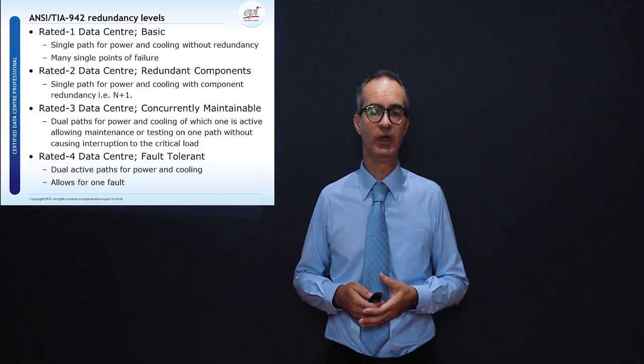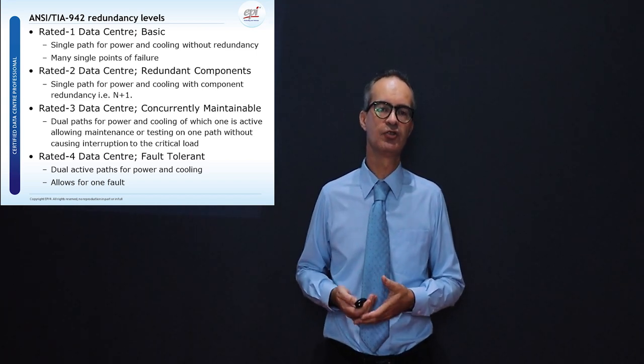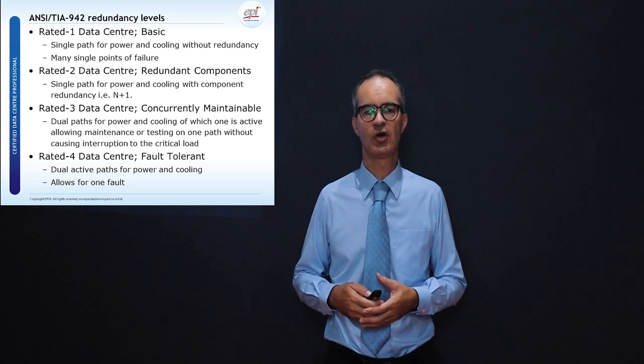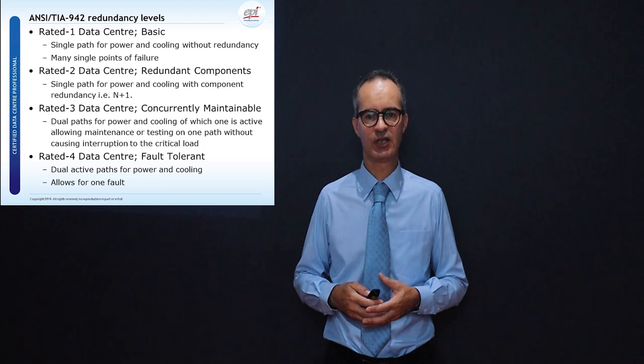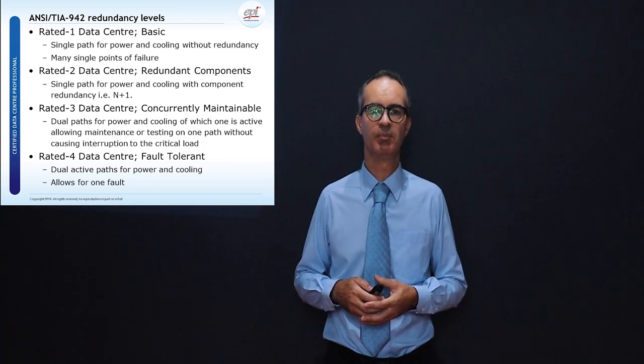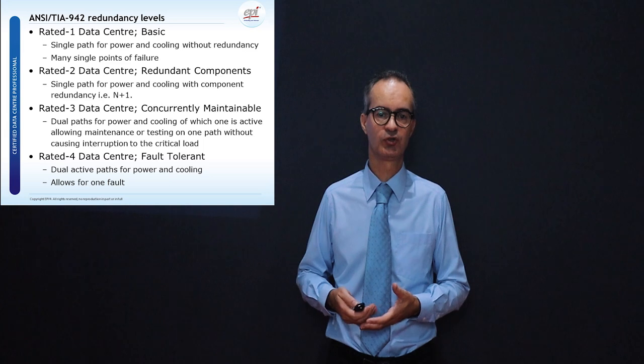In chapter two we talk about standards, and one of the leading standards in the industry is ANSI TIA 942. This standard discusses so-called rated levels, and with every number going up it is believed that we have a higher expected availability — from Rated 1, which is very basic, up to Rated 4, which is considered fault tolerant.